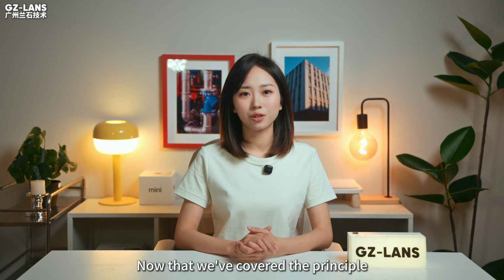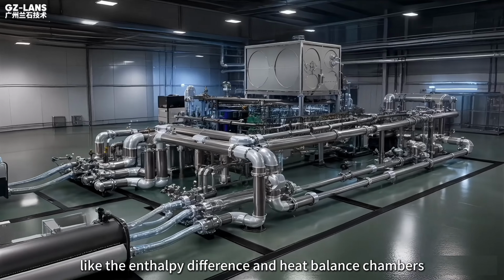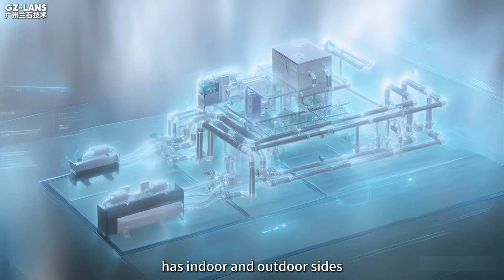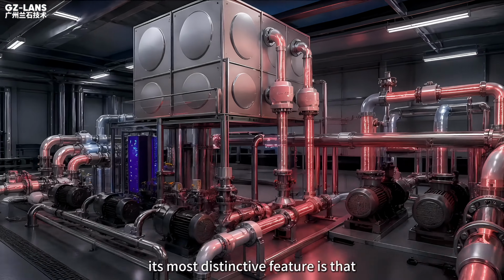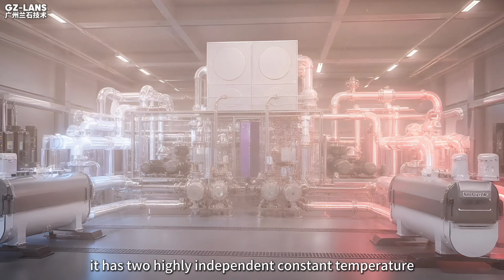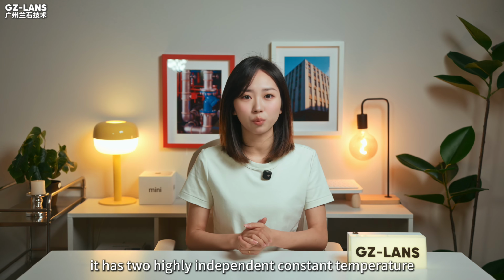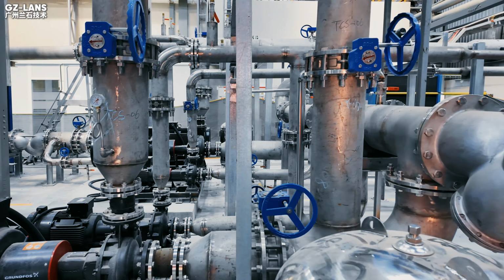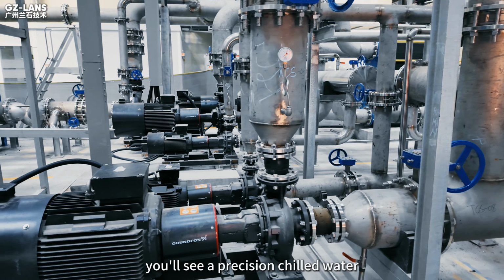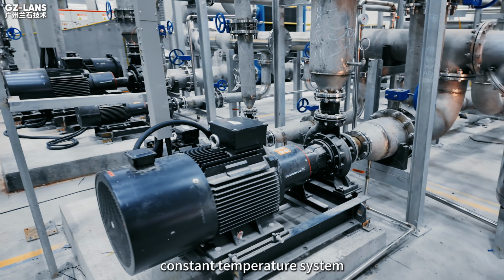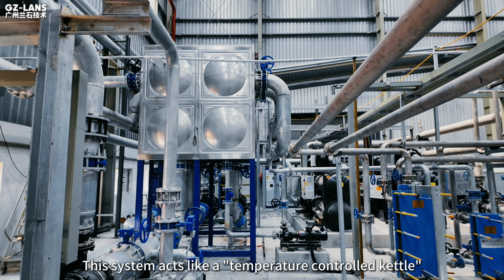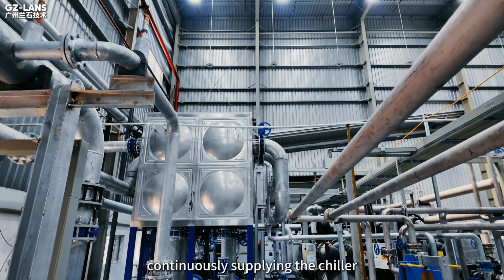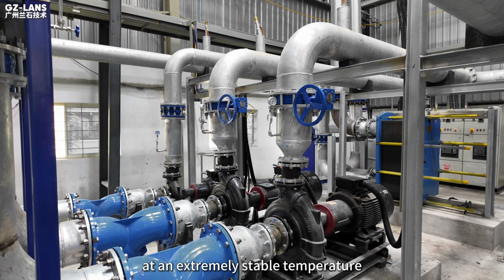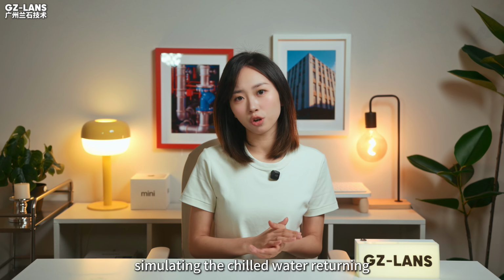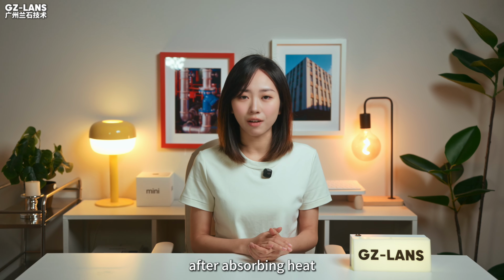Now that we've covered the principle, let's look at its structure. Like the enthalpy difference and heat balance chambers, the water-cooled chiller test lab has indoor and outdoor sides, but its most distinctive feature is that it has two highly independent constant temperature water systems. On the indoor side, instead of an air handling unit, you'll see a precision chilled water constant temperature system. This system acts like a temperature-controlled kettle, continuously supplying the chiller with return water at an extremely stable temperature, simulating the chilled water returning from the air conditioning terminals after absorbing heat.